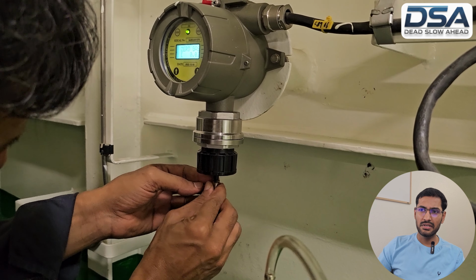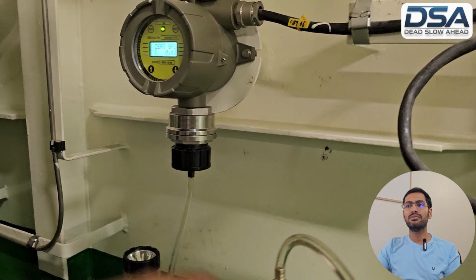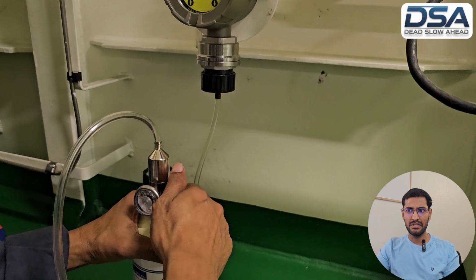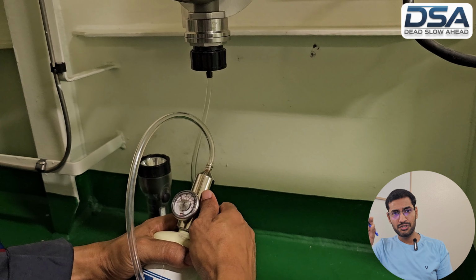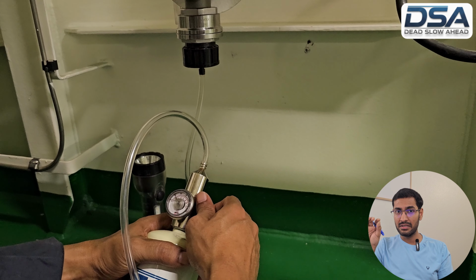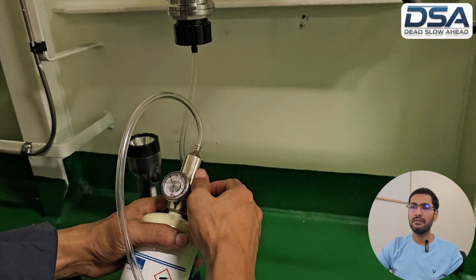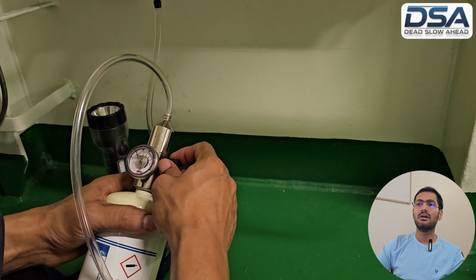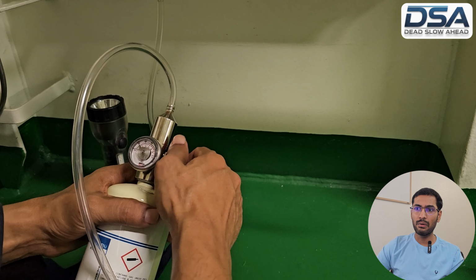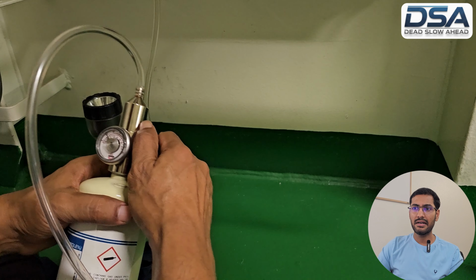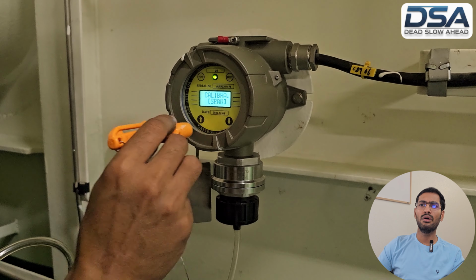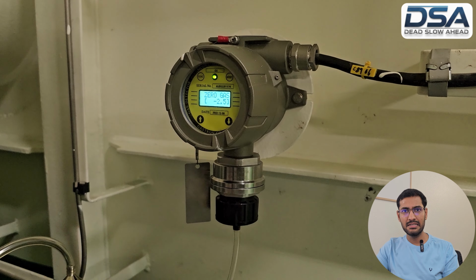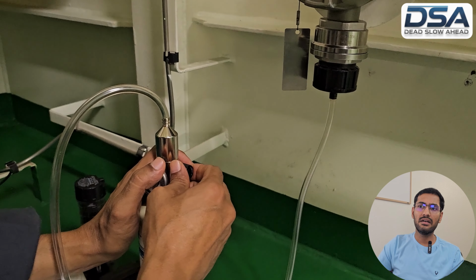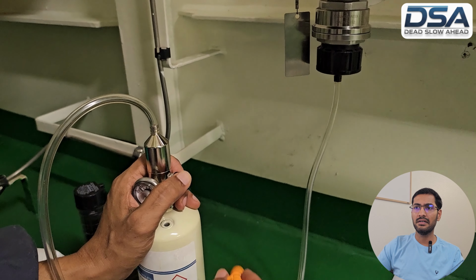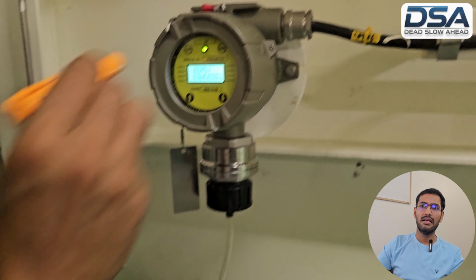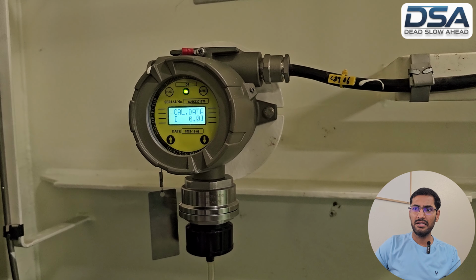Now we perform zero calibration. As you can see, we have connected a nitrogen cylinder with the proper hose connection, and it is very important to ensure that the correct gas flow is there. You need to verify the manufacturer specification for how many liters per minute of gas is required for proper calibration. Once the reading stabilizes at 0 percent, you can confirm the reading, and it should display success, and the zero calibration is finally over.